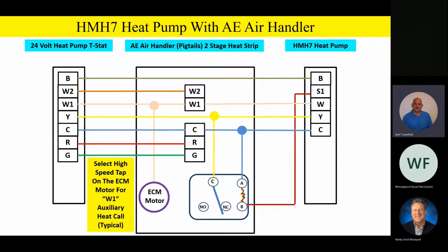So basically, anytime you get an auxiliary heat call or anytime you go into defrost, we're going to drive that fan to 100, not 100% airflow, but just a high speed airflow, whatever that happens to be. Now watch this. On the normally closed contacts, in other words, the relay is just sitting there. It is not energized yet. You haven't energized A and B, or the coil. You haven't energized or switched this relay. The normally closed contact on the relay is going to go to a speed tap. You're going to select a speed tap on the ECM motor to give you 100% cooling airflow.